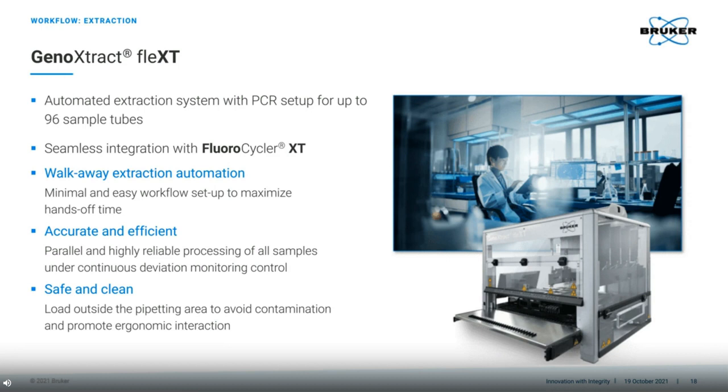The GenoXtract fleXT was launched in April 2021. It is a reliable medium to high throughput extraction device with automatic PCR setup, which means it can be used seamlessly with the Fluorocycler XT, with minimal manual intervention needed from extraction to results. After a short setup, the samples, chemistry and various parts needed for the extraction and PCR setup are placed on the external docking tray. The software guides the user through the few steps needed, and the robotic arm puts the parts where they are required inside the device. Once running, you can move on to other tasks.